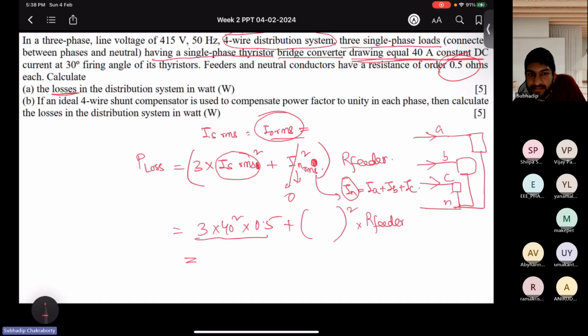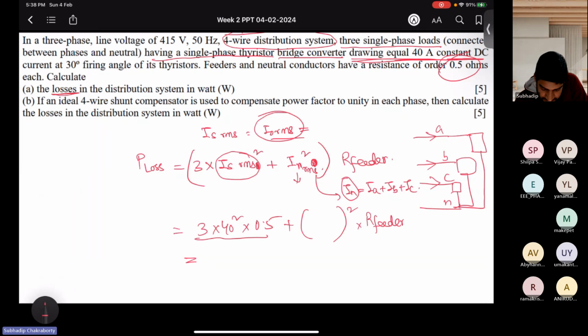Because the loads are symmetric and balanced. Anyone wants to say anything? This is an important point, right? So it will not be 0. Just rethink. Although you have similar kind of loading in the 3 phases, I am claiming that the neutral current will not be 0. Why is it so? Anyone? In this kind of problem, don't be misled. Since you have similar loading does not necessarily mean that the neutral current will be 0. Why so? Again, come to the waveform.